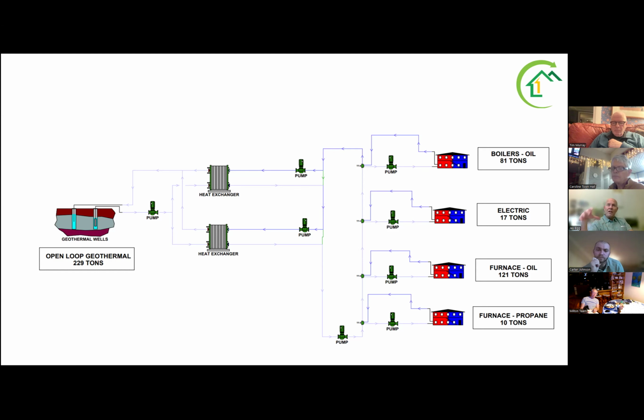Some wanted individual room heat pumps, like what you'd see in a Days Inn with a heat pump under the window - those are actually very quiet when they're geothermal, you can't even hear them. But you can do room-by-room heat pumps, which they call package terminal heat pumps, or a central forced air system, which would require running ductwork to all the rooms if you don't already have it. They did any number of variations of those, and many required upgrading the panels because they didn't even have air conditioning before, and now they have both air conditioning and heating.